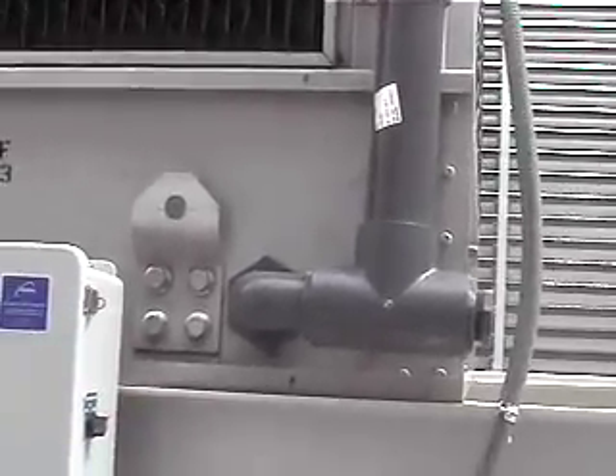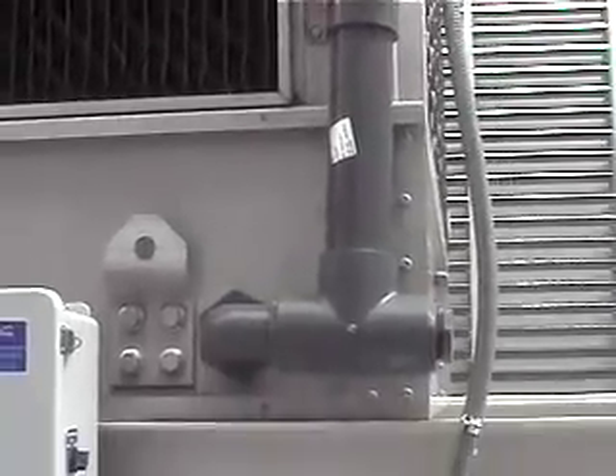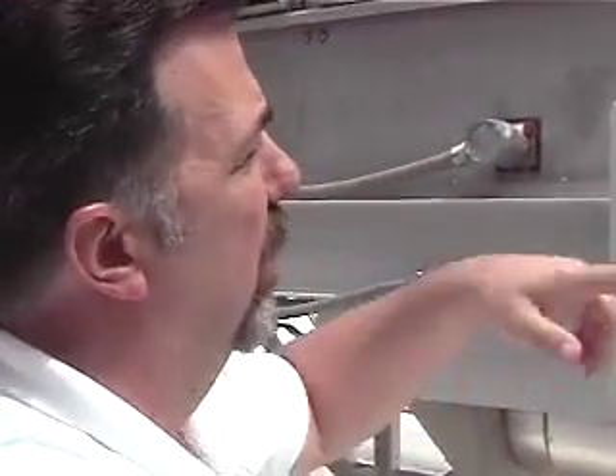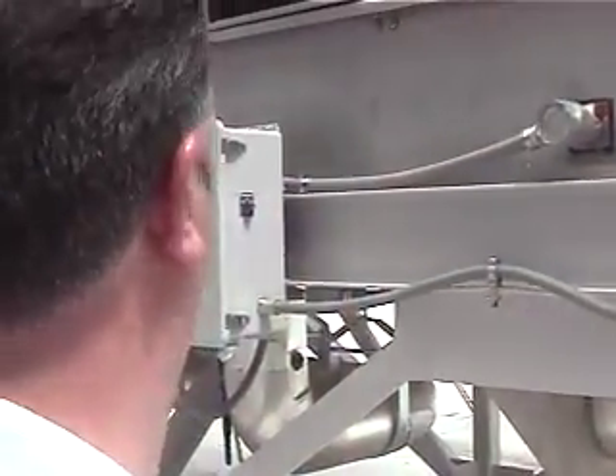that plugs out, you can actually open it up. A lot of water will come out right now, of course, but you can see the longer probe. If you look in the top there, take the lid off the top, you can see the probe going down into it. What kind of probe is it? It's an electrode. Oh, so there's one that's actually the common, and then you've got 4 more at different levels. So all it does is just make the circuit when the water gets to that level. Okay. Is it a Borek sensor? I think so. Okay.